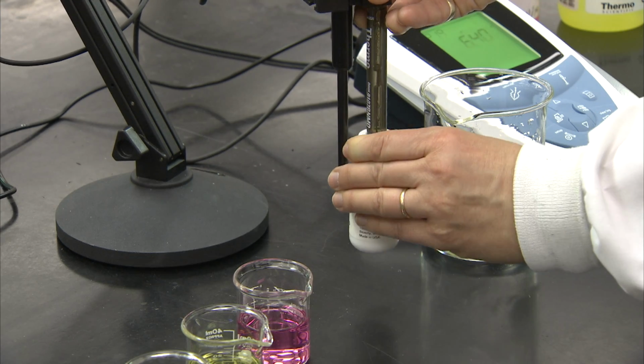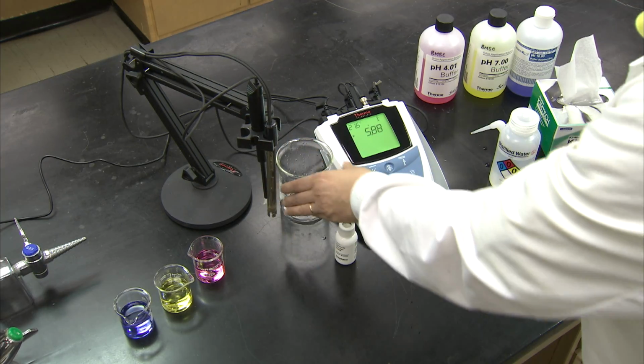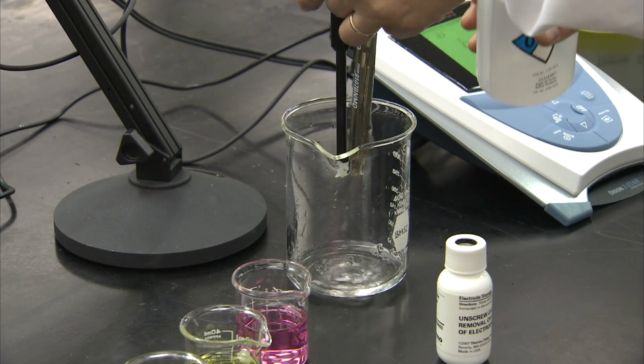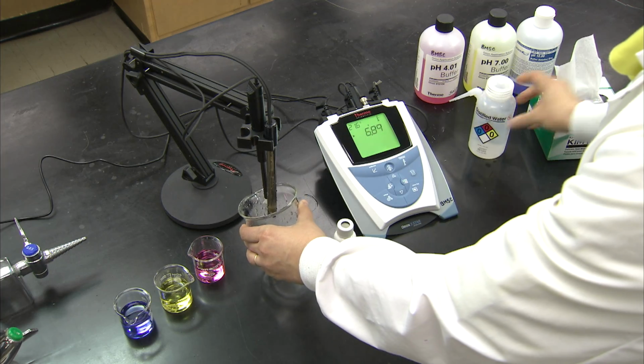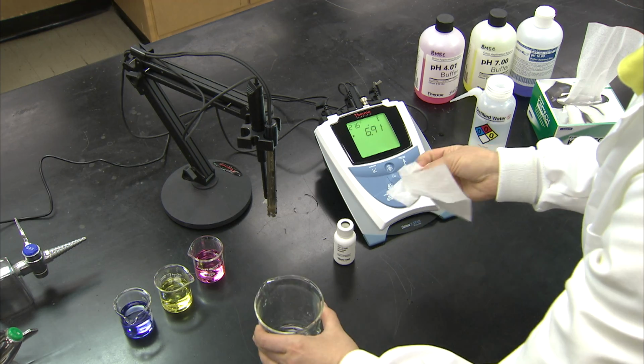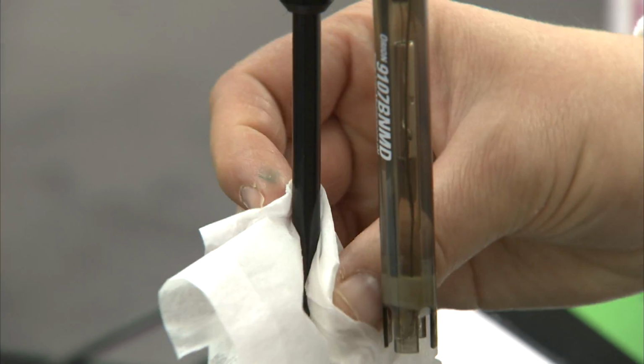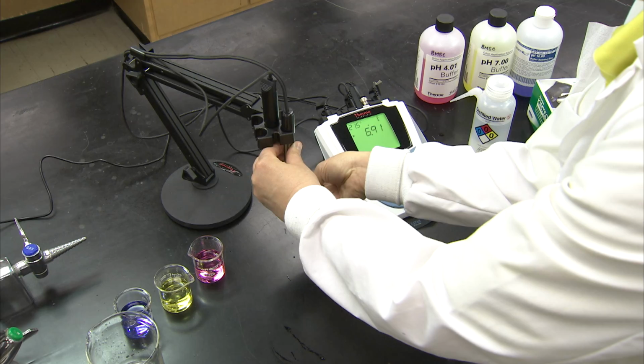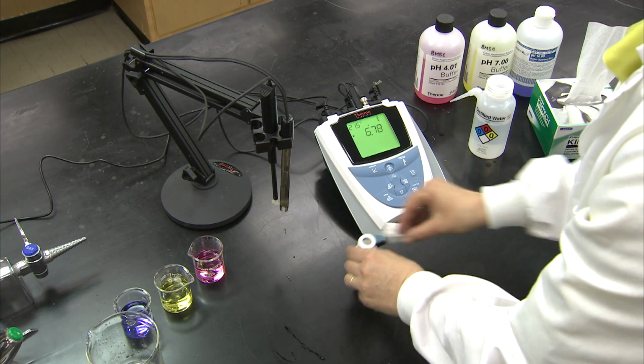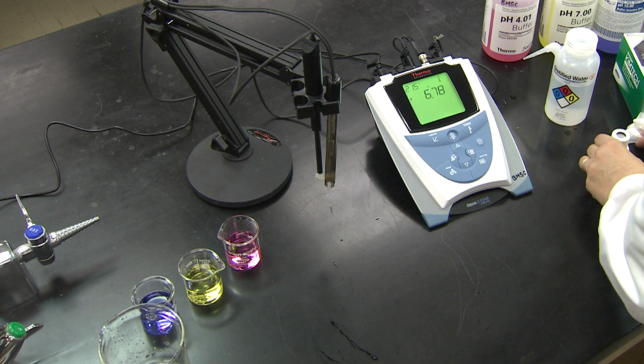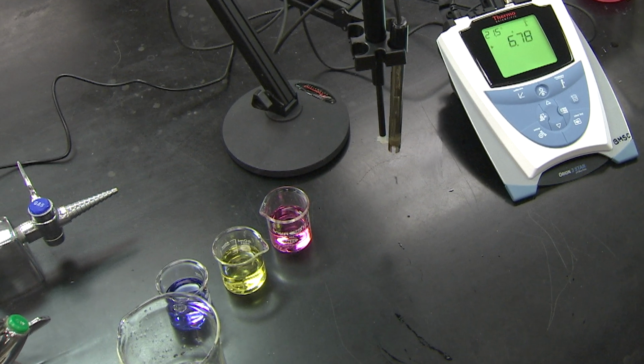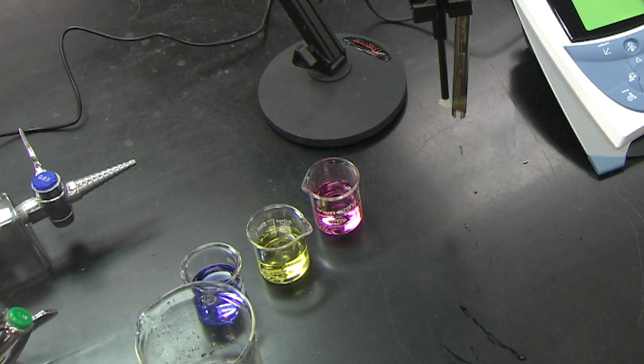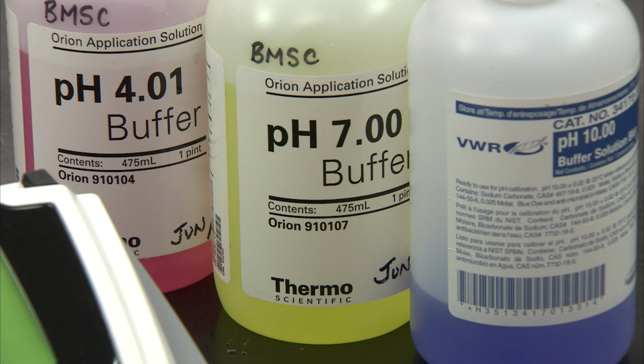The probe is removed from the bottle and rinsed off. Then, the outside is wiped off with a Kim wipe. Carefully dab the probe without scratching it. The probe will now be immersed into each of the calibration solutions. Depending on the range of pH values to be measured, this is a 2-point or a 3-point calibration. These standards are purchased from a manufacturer and are accurately pHed to 2 decimal places for the most reliable calibration.